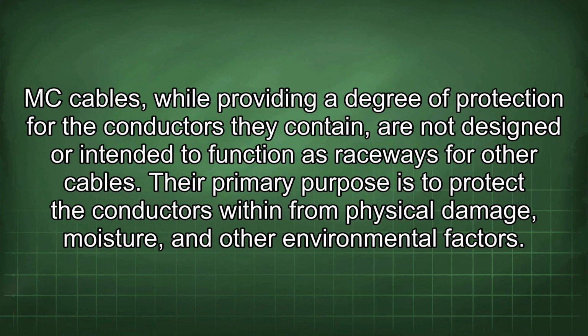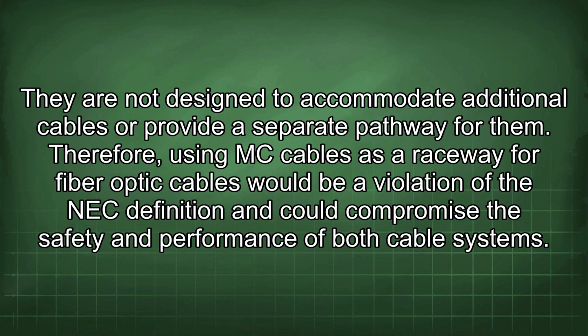MC cables, while providing a degree of protection for the conductors they contain, are not designed or intended to function as raceways for other cables. Their primary purpose is to protect the conductors within from physical damage, moisture, and other environmental factors. They are not designed to accommodate additional cables or provide a separate pathway for them. Therefore, using MC cables as a raceway for fiber optic cables would be a violation of the NEC definition and could compromise the safety and performance of both cable systems.